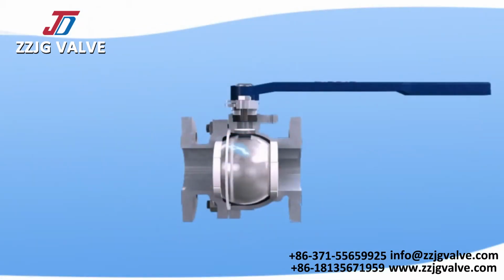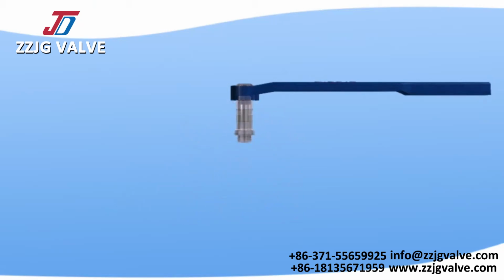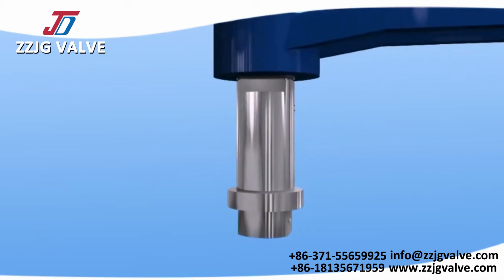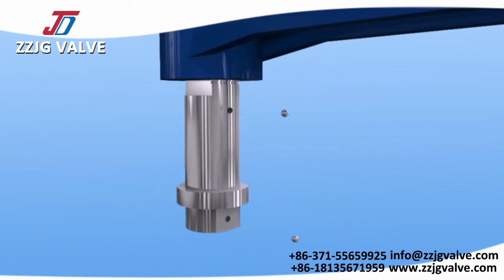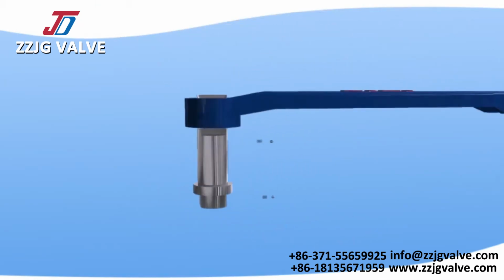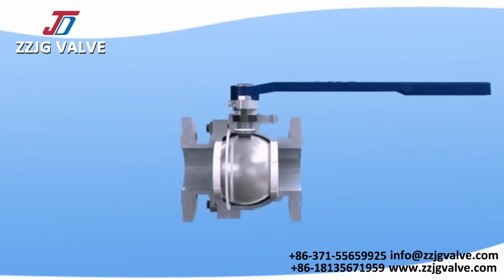3. Valve anti-static device. When operating the valve, the friction between the ball and the non-metal seat will produce an electrostatic charge that will accumulate on the ball. To prevent static spark, an anti-static device is placed on the valve to conduct the electric charge away through the static channel between the ball and the stem or between the ball and the body.